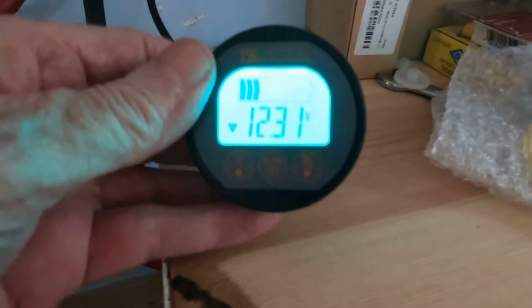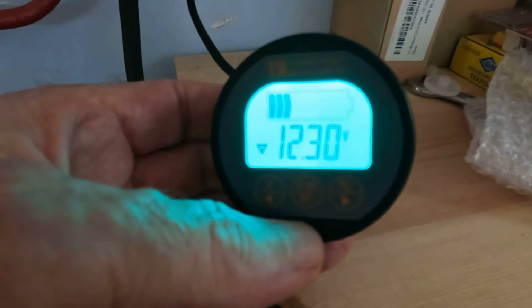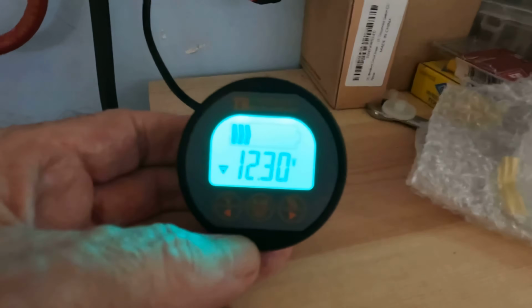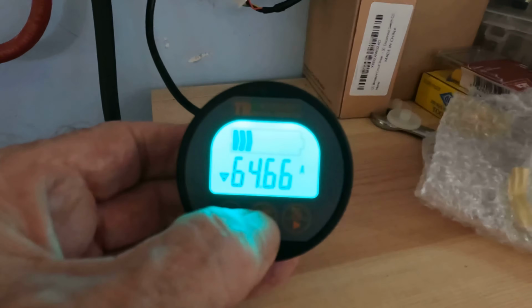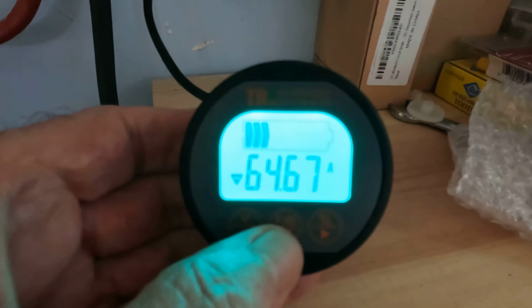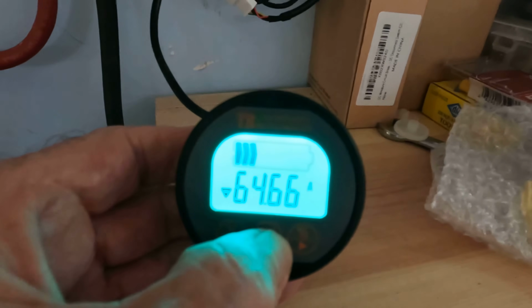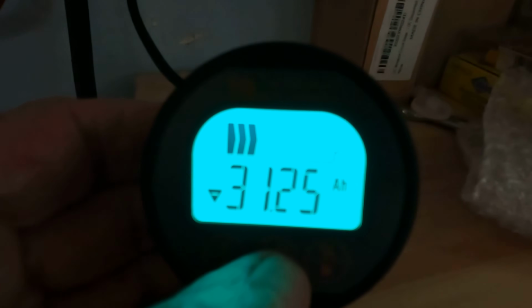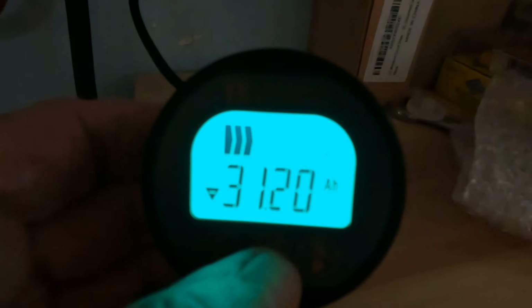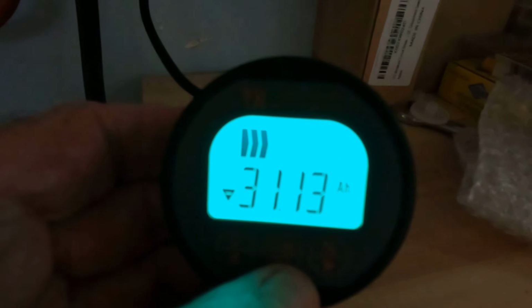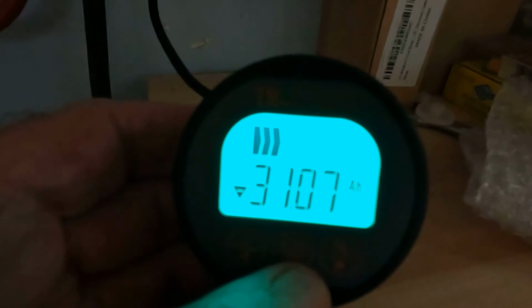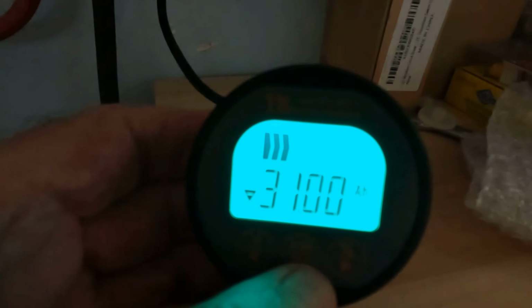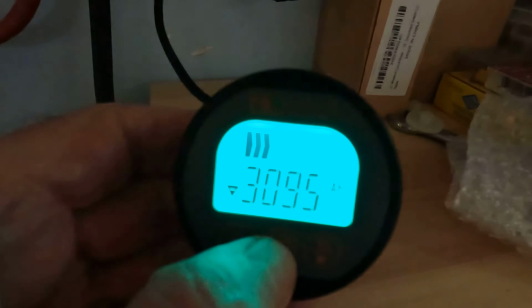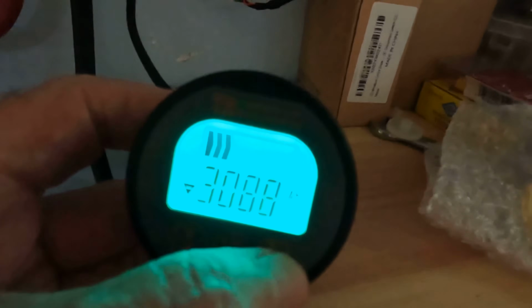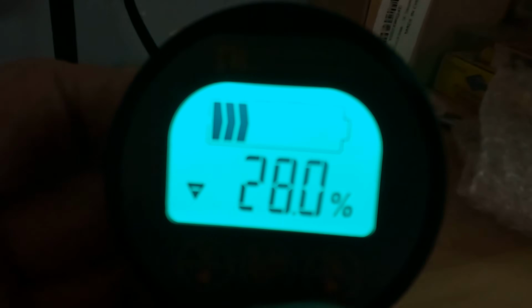Okay, it's been about an hour and 15 minutes I guess. I have the timer going, and we're at 12.3 volts. We're still pulling 64.6 amps off of this battery, and it now shows from 110 amp hours where we started, we're down to 31 amp hours now, and you can see it dropping in increments of 2 or 3 pretty quick as it's pulling still that 740 watts. It's been pretty consistent on that, and it says we're down to 28% full.